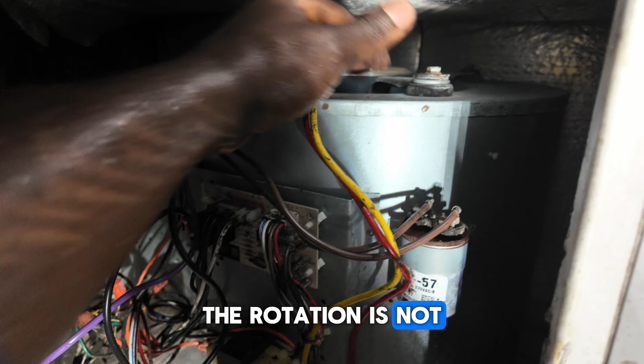Now, there are several ways to test if this motor is working at this point. I can actually test it. First, I have set my hands here based on what the customer said. This is kind of stuck. It's actually stuck. The rotation is not good. That means that motor is not good.